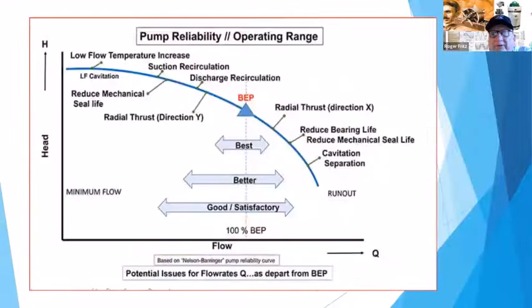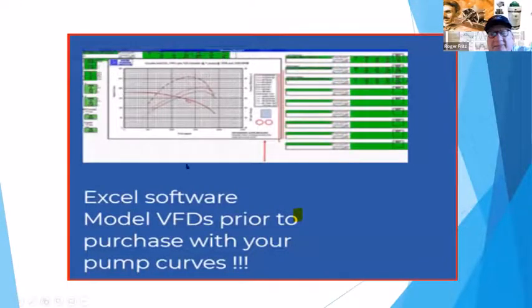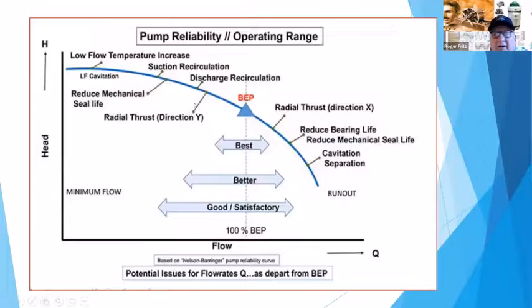And so there is a software tool. This was developed by a guy named Rob Wilkie, who's out of Australia, that I met. He's got it so that you can plug the various points in. You can set up those various scenarios so we can find out when we change it to that speed, we go to that GPM, it shows where that sweet spot went, and whether you have the right design for that motor based on what your actual load is, so that we get our optimal best brake horsepower functioning all the time.